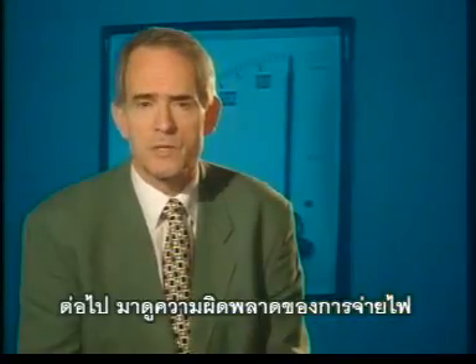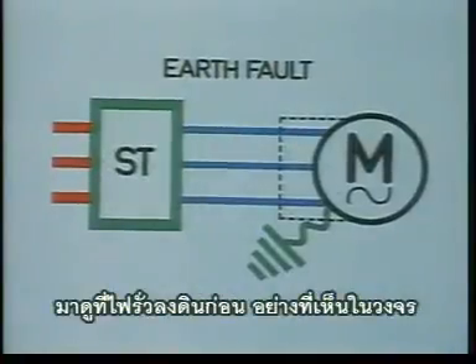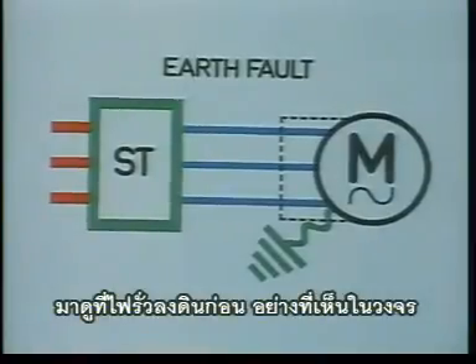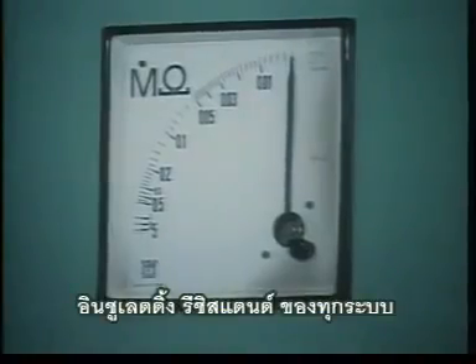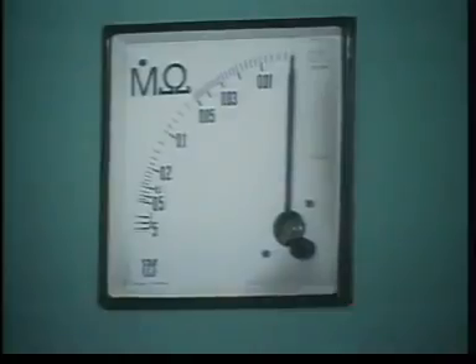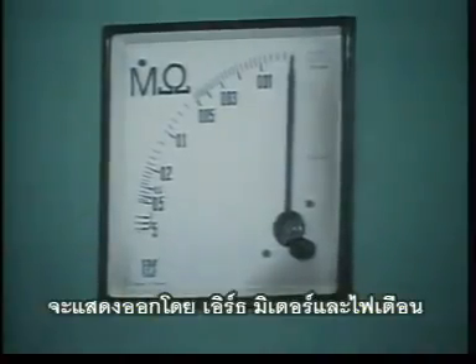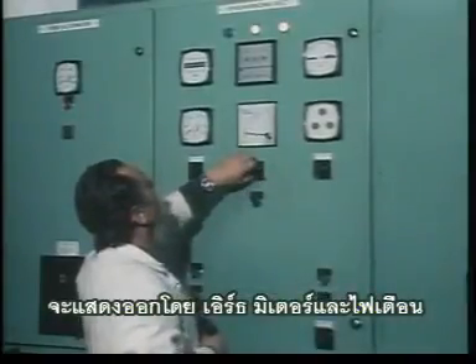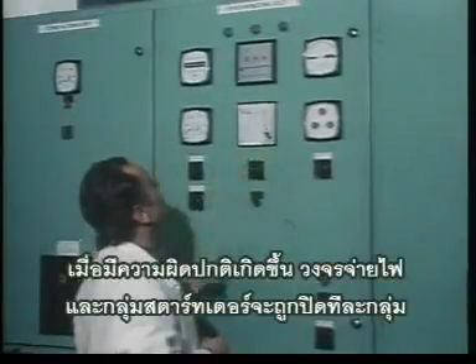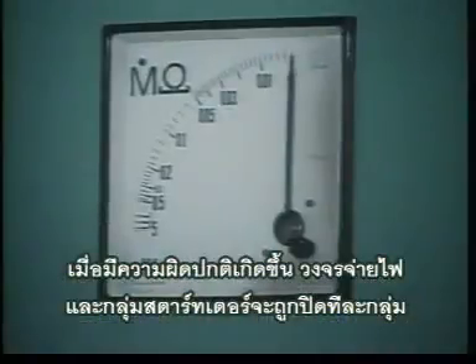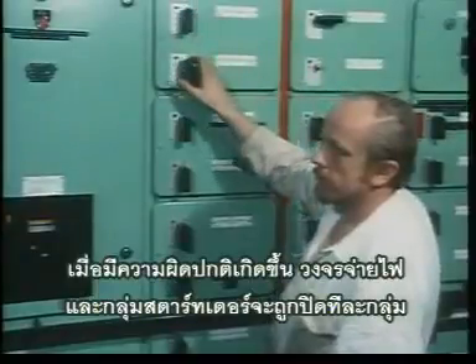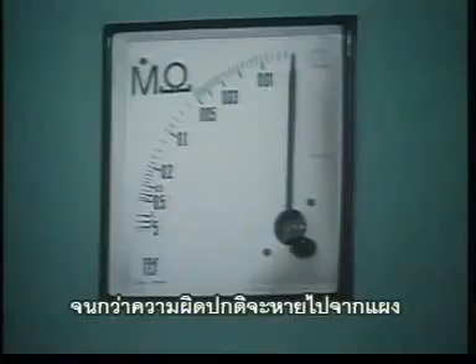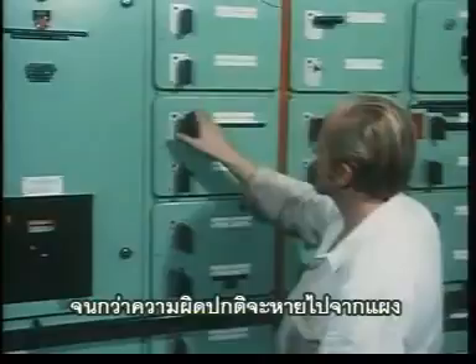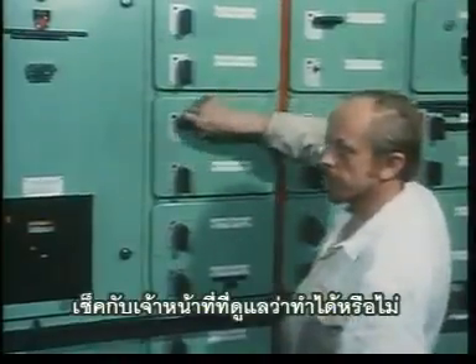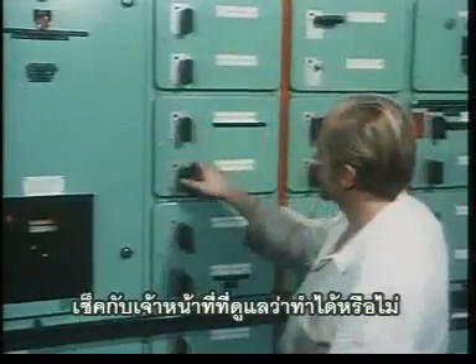This brings us to distribution faults. Earth fault first, as seen here. The insulation resistance of the entire system is monitored by an earth meter and earth fault lamps. When a fault appears, the feeder circuits and group starters are switched off one by one until the fault indication disappears on the board, checking first with the officer on watch that it is practical to do so.